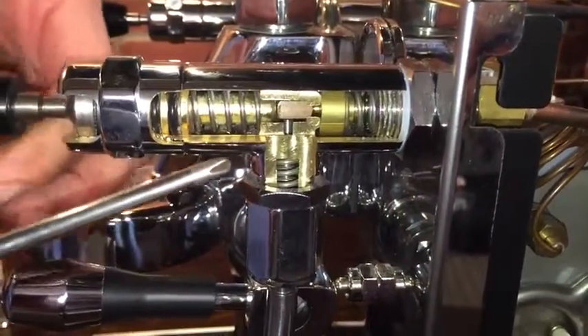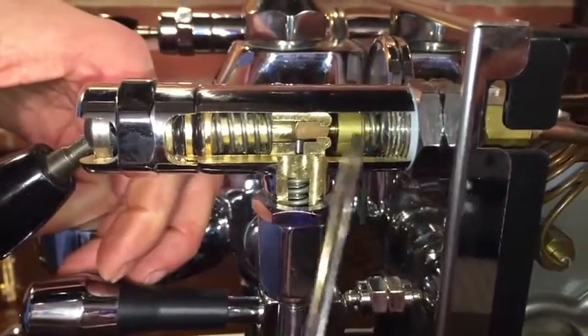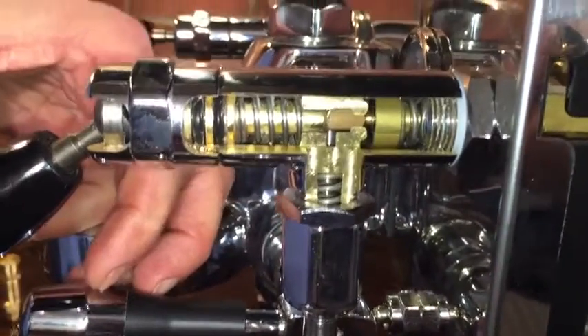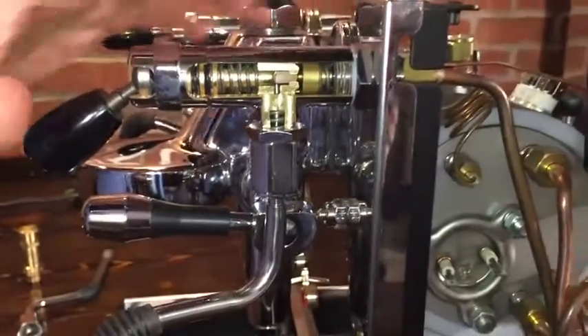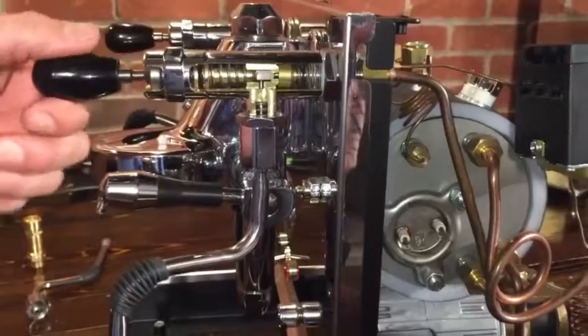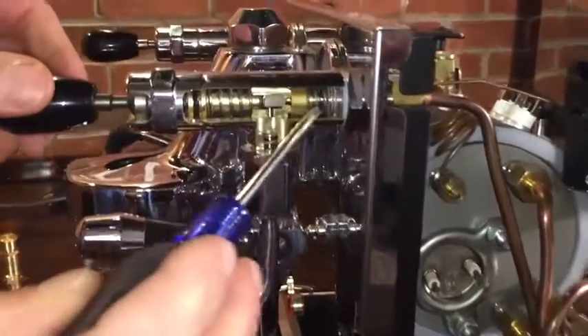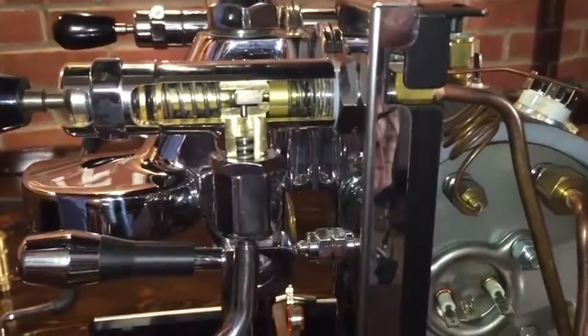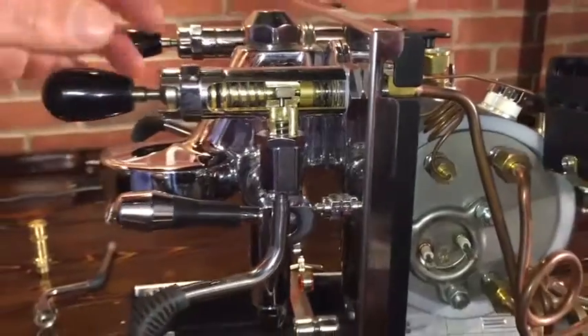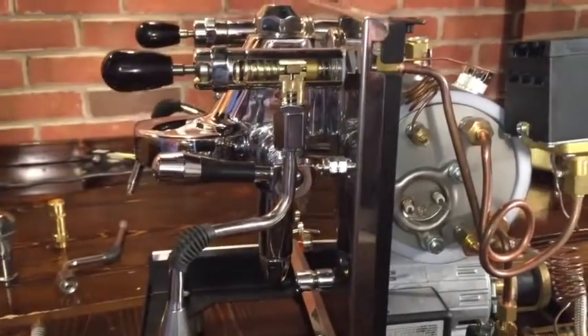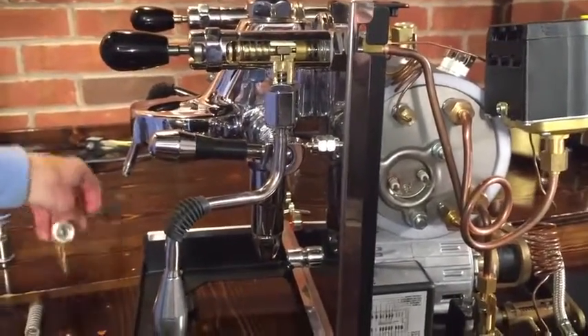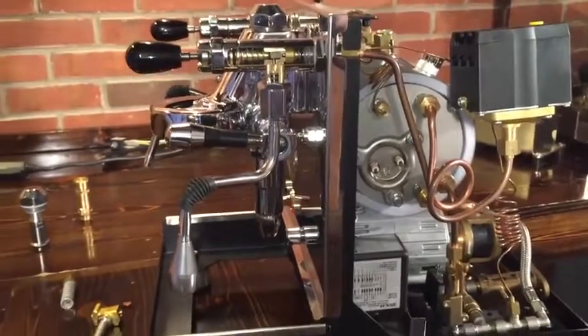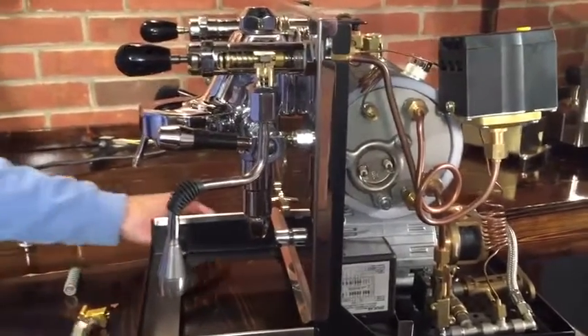But when you open this, it allows the pressure to come through and out and down, whether it's steam or hot water. So it's nice—the only pressure holding this on here is just the spring. So it's not like screwing down a valve where you screw it constantly and you can overpressurize it and damage the valve. With the spring, it's more reliable, a longer lasting sort of setup.